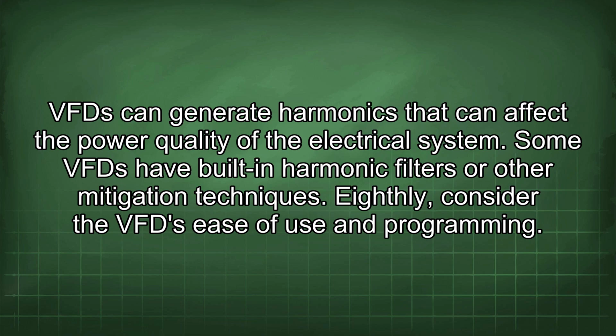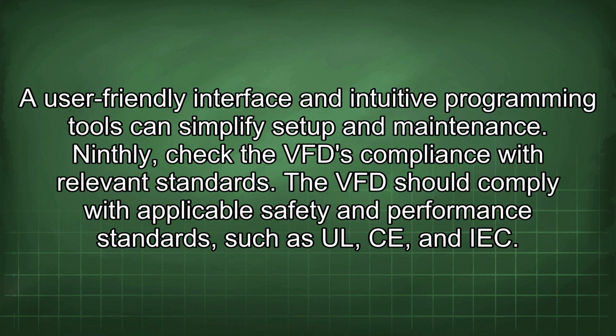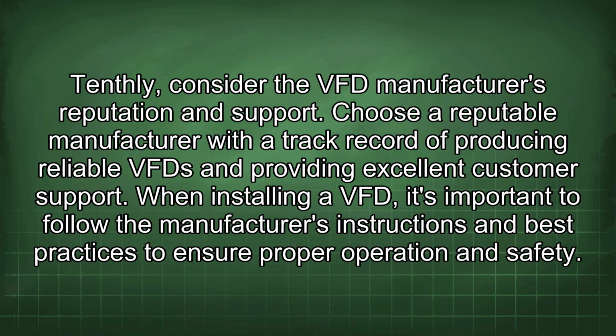Eighthly, consider the VFD ease of use and programming. A user-friendly interface and intuitive programming tools can simplify setup and maintenance. Ninthly, check the VFD compliance with relevant standards. The VFD should comply with applicable safety and performance standards such as UL, CE, and IEC. Tenthly, consider the VFD manufacturer's reputation and support. Choose a reputable manufacturer with a track record of producing reliable VFDs and providing excellent customer support.